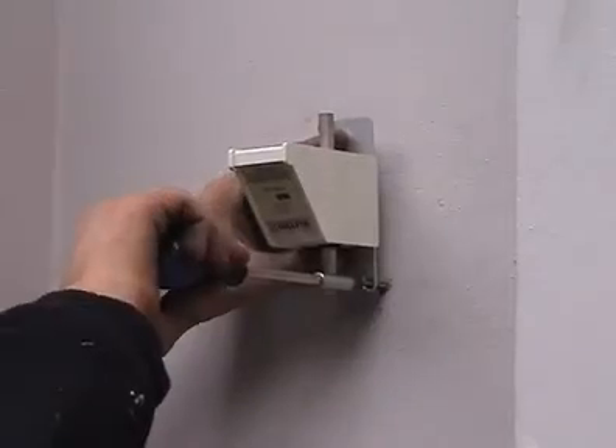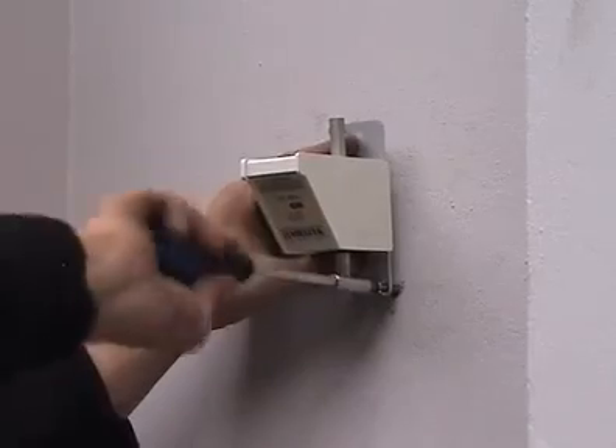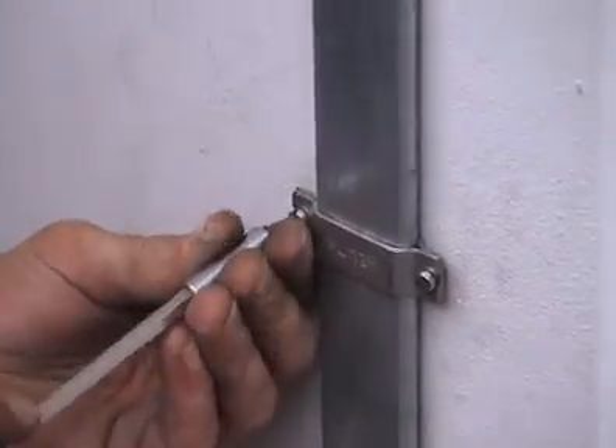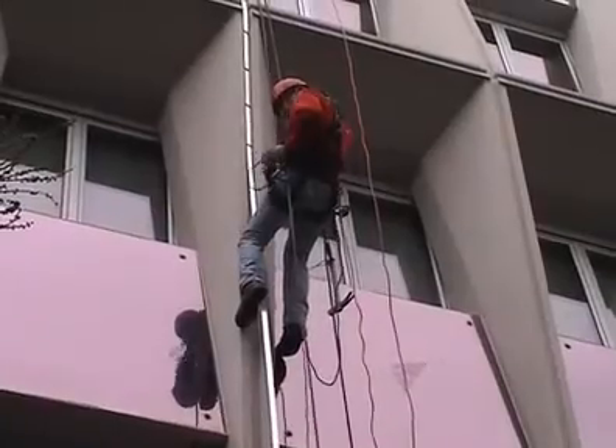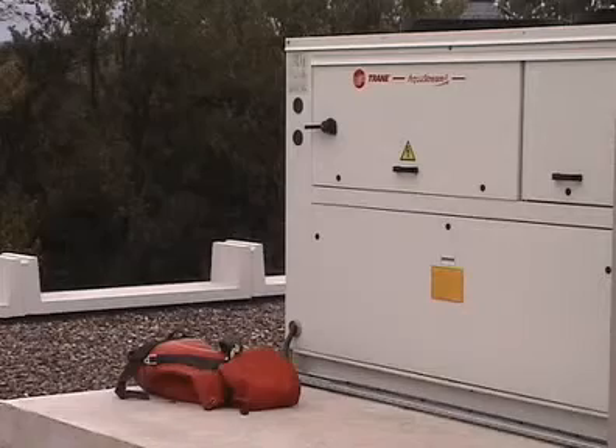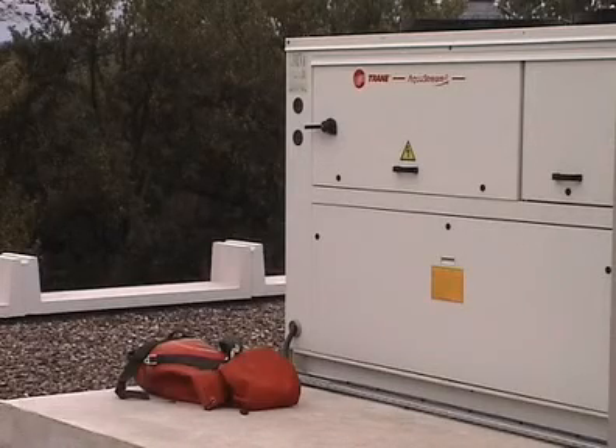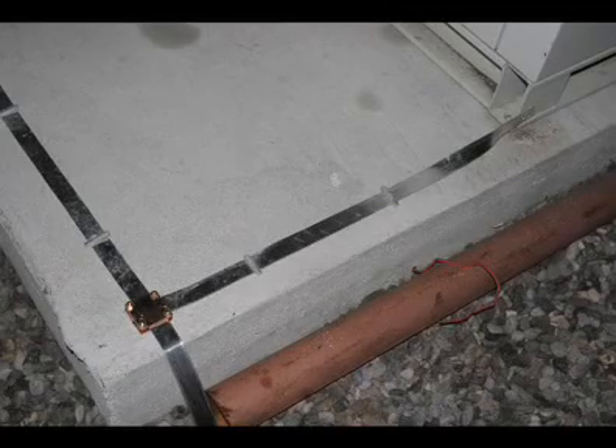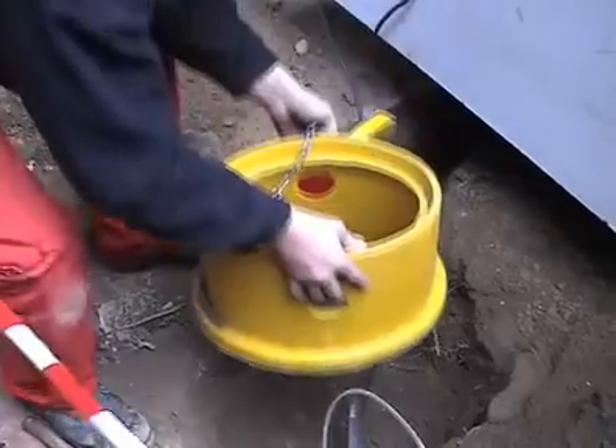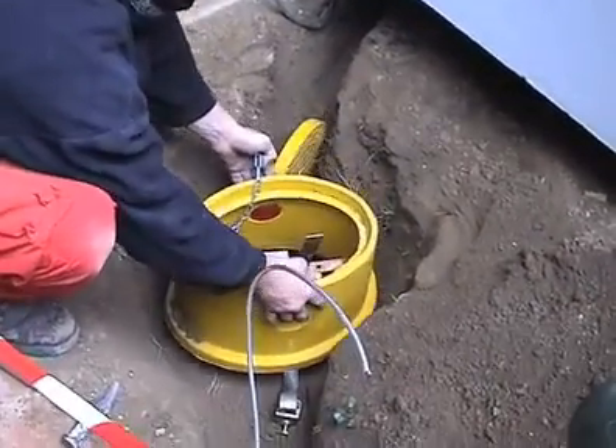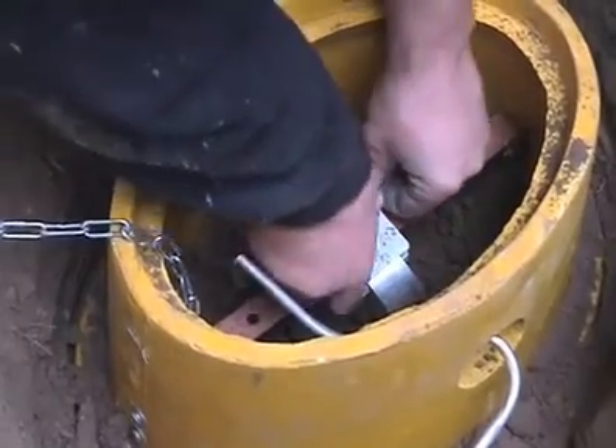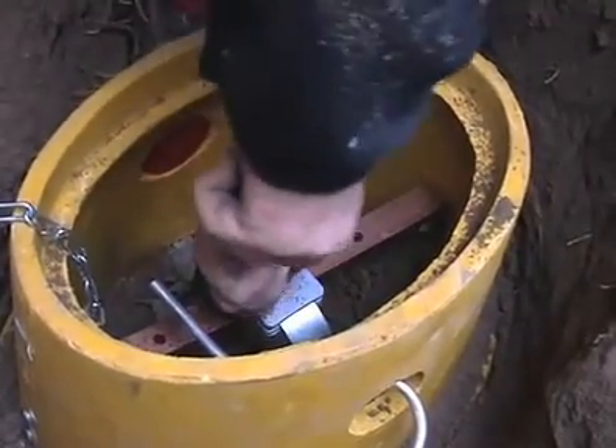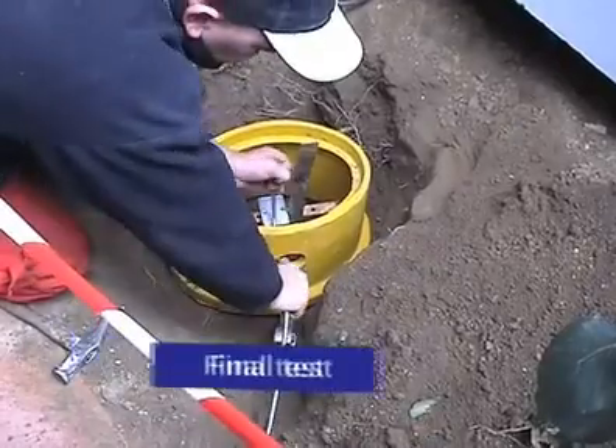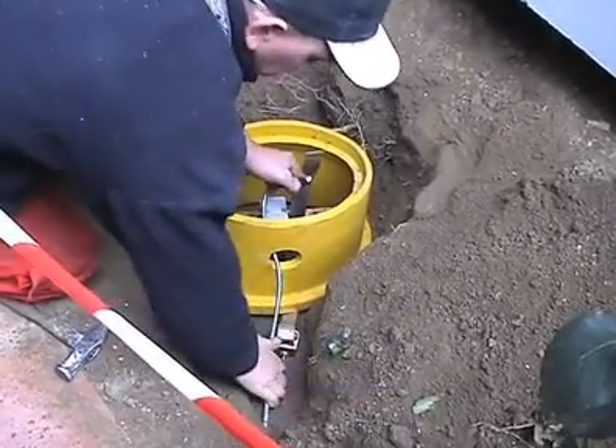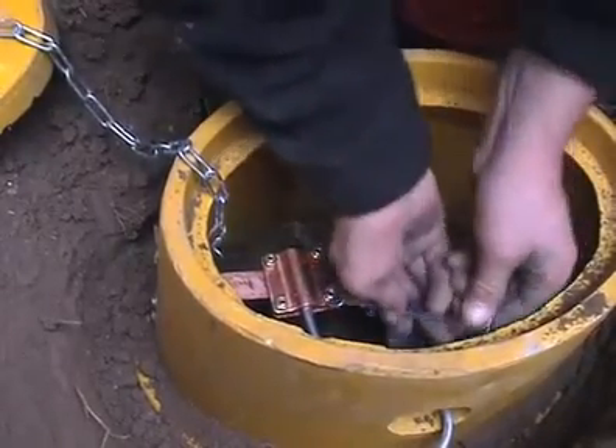We now have to install the lightning strike counter onto the wall and connect it to the flat protecting tape. We also have to connect all the down conductors to every metal part connected to the ground in order to avoid any flashover. Place the inspection earthing pit into the ground and connect the down conductors to the earthing system. Insert the test coupling in order to isolate the earthing system from the rest of the installation while taking measurements. Connection in the earthing pit is completed between the building's electrical earth and the lightning's earth system.